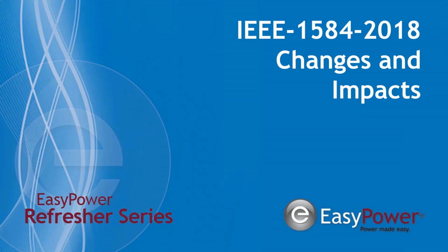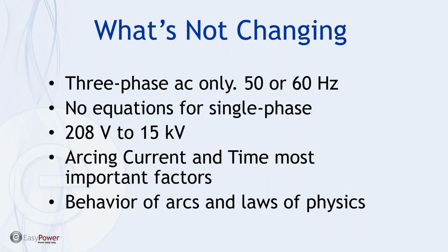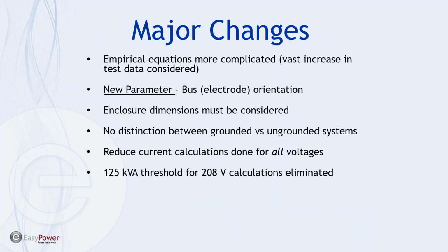Now I want to talk a little bit about the changes in the 1584 model because they directly impact the data collection process, in that there are typical values recommended by the standard, but there are places where a non-standard or customized panel or piece of switchgear could affect the incident energy being calculated. So what's not changing is that the target is still three-phase AC only as far as modeling. The model is only good for 50 or 60 hertz. There's still no equation for single phase, and the voltage range is 208 volts up to 15,000 volts. Arcing current and time are still the most important factors in calculating incident energy, and again, the behavior of arcs and the laws of physics haven't changed at all either.